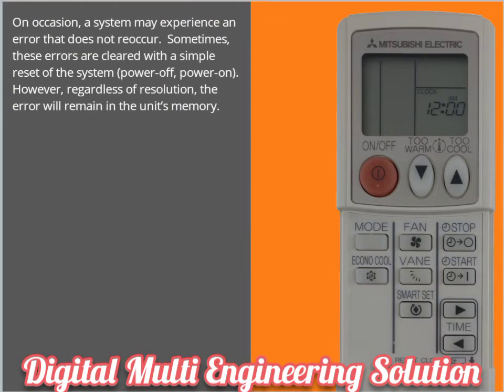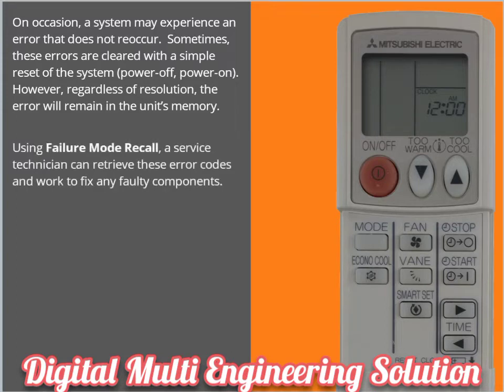On occasion, a system may experience an error that does not reoccur. Sometimes, these errors are cleared with a simple reset of the system, power off, power on. However, regardless of resolution, the error will remain in the unit's memory. Using Failure Mode Recall, a service technician can retrieve these error codes and work to fix any faulty components.